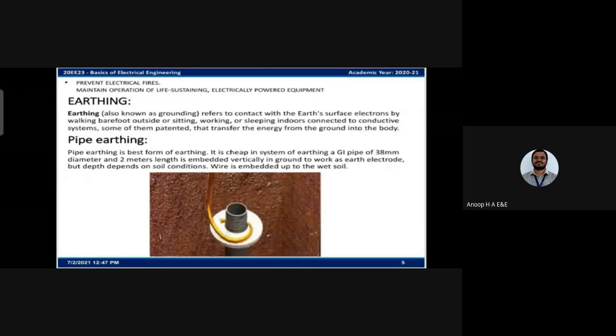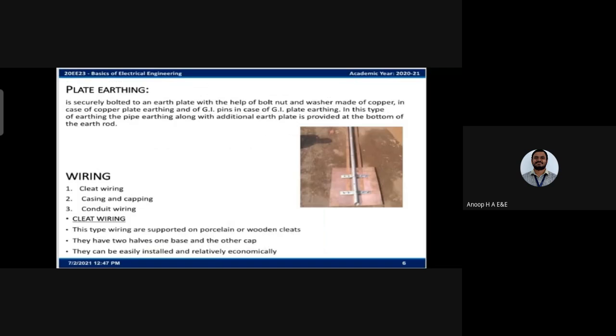Earthing. Earthing, also known as grounding, refers to contact with the earth's surface by electrons, by walking barefoot outside or sitting, working, or sleeping indoors connected to conductive systems. Types of earthing. Pipe earthing is the best form of earthing because it is cheap and very efficient when compared to plate earthing. Plate earthing is a type where the earth wire is securely bolted to an earth plate with the help of a bolt, nut and washer made of copper in case of copper plate earthing, and of GI in case of GI plate earthing. In pipe earthing, an additional earth plate is provided at the bottom of the earth rod.